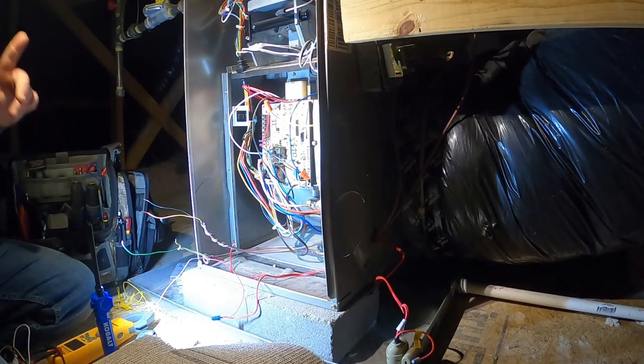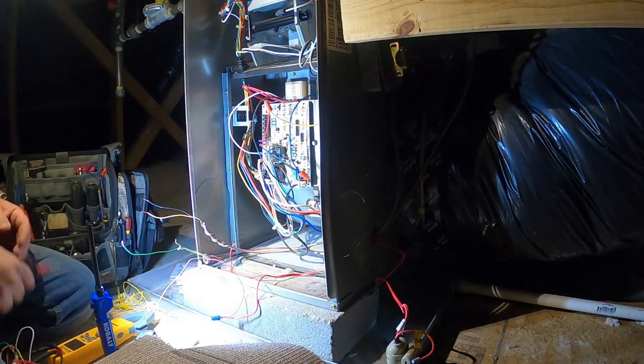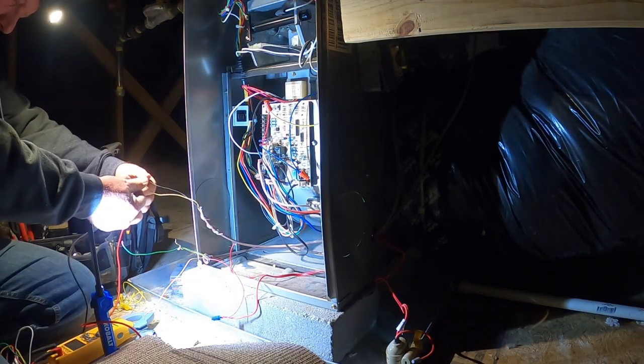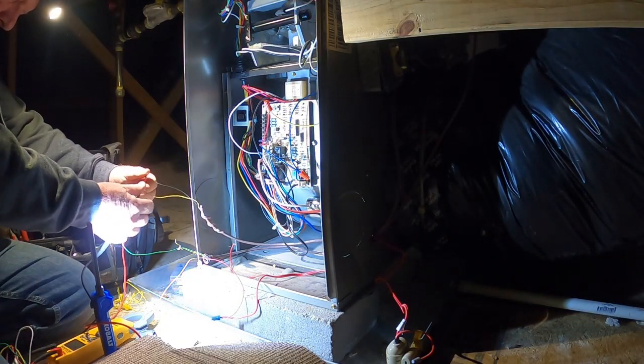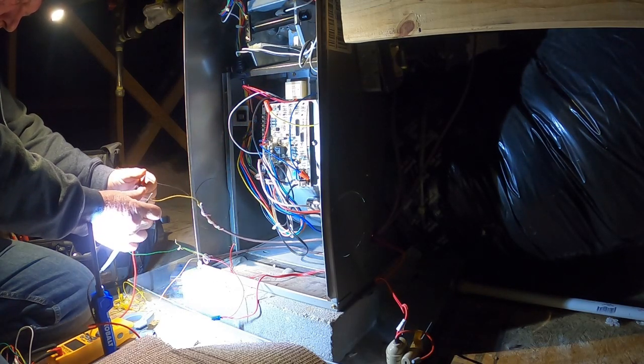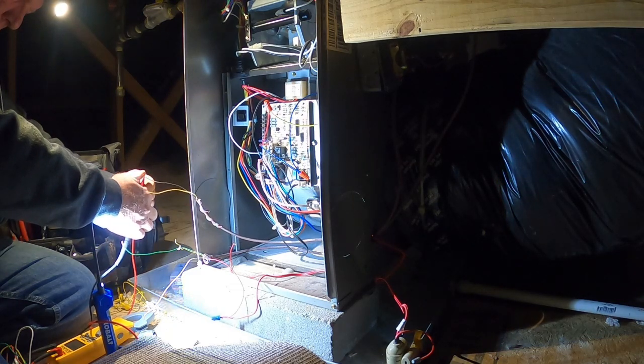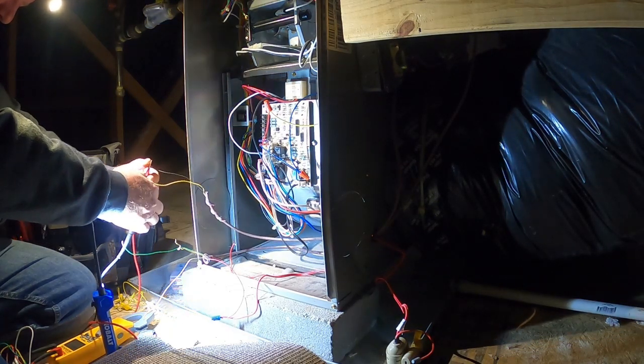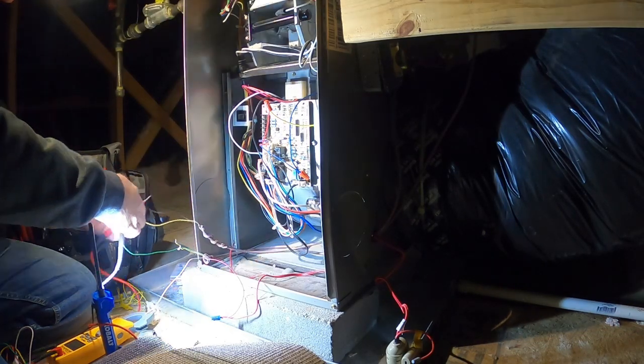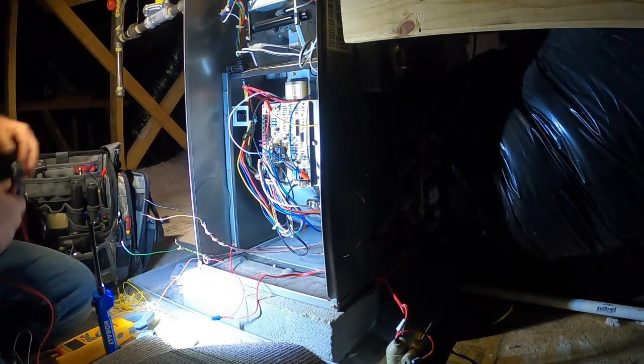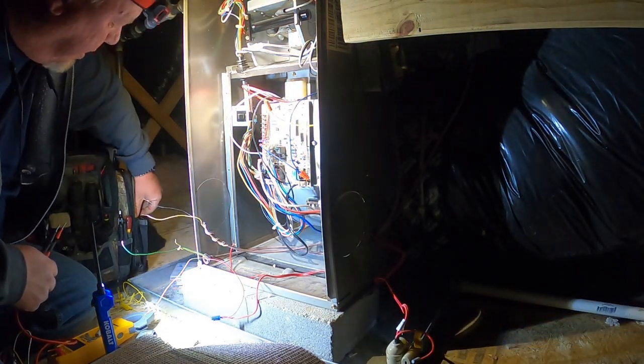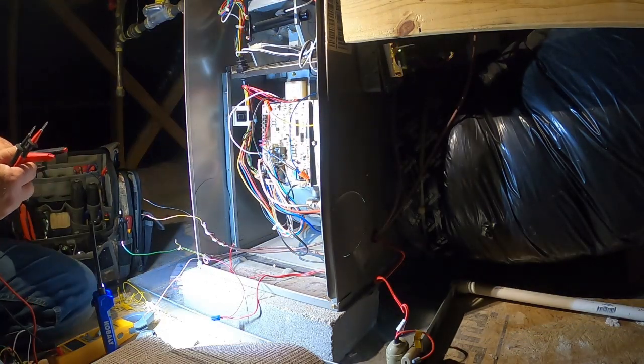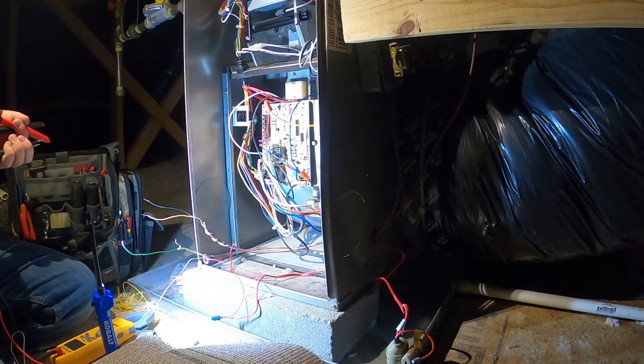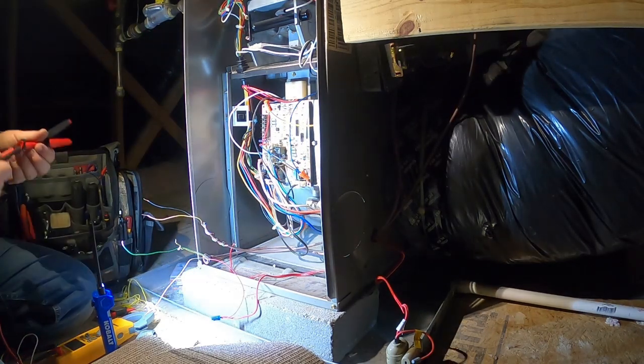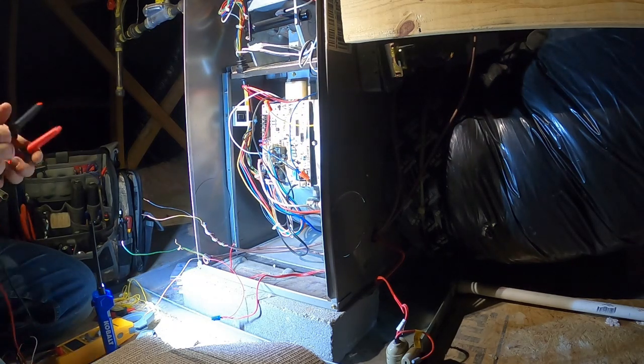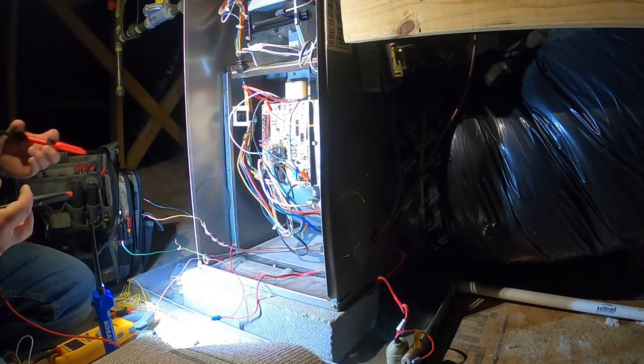Alright, we're back up in the attic. Contactor outside is replaced. Check my ohms back through these wires real quick. Let me get through my alligator clips. Sometimes if you get your fingers on it, you're getting, I want it to reach somewhat close to what it was outside. It is going through wired back through a load management. The low voltage goes through a load management box. And that may be the slight discrepancy I'm getting up here now.